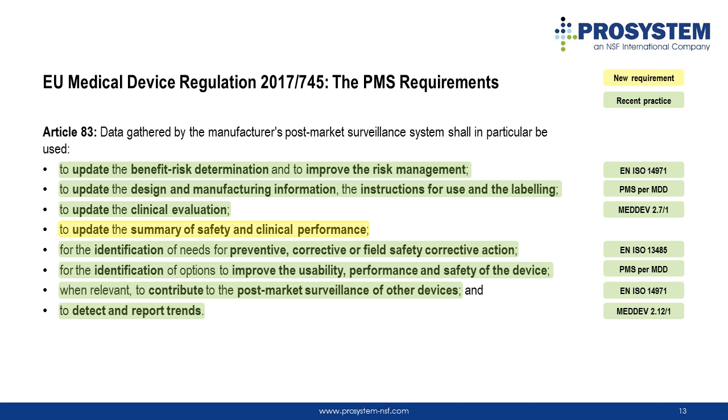The SSCP report must also be updated whenever updates to the risk management, clinical evaluation, or other accompanying documentation for the eyes of the public are required. PMS data has a potential to identify the need for CAPAs or FSCAs to improve usability or product performance and safety. The data should furthermore be evaluated whether it may contribute to the PMS of other devices that the manufacturer places on the market, and very importantly, to the detection of trends.